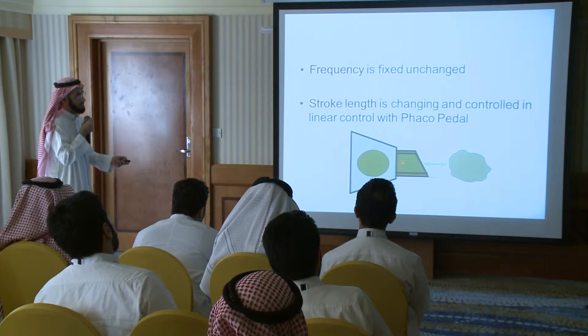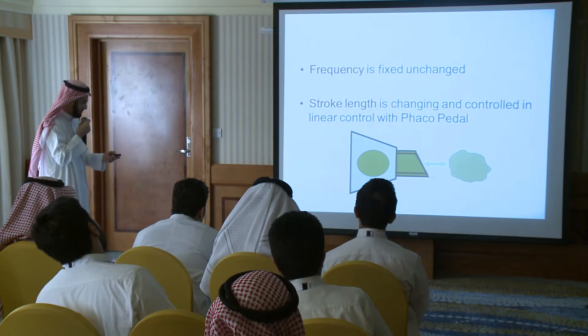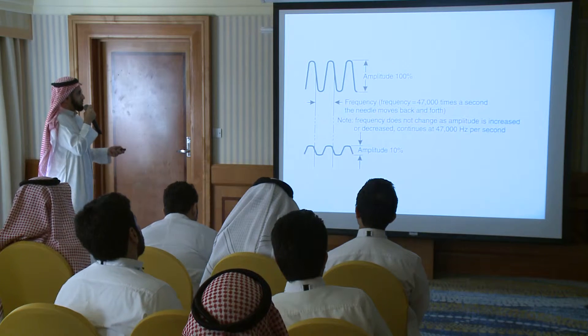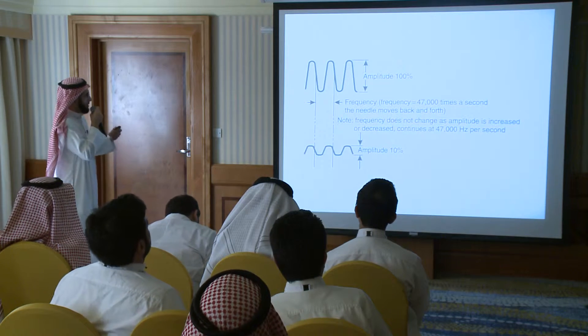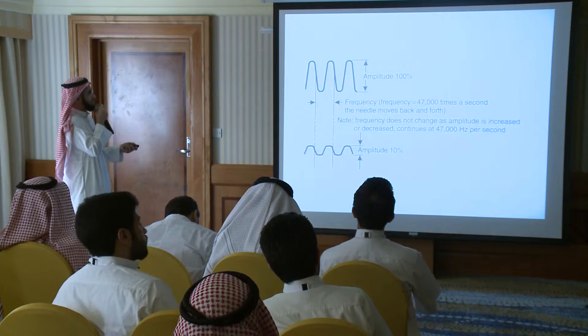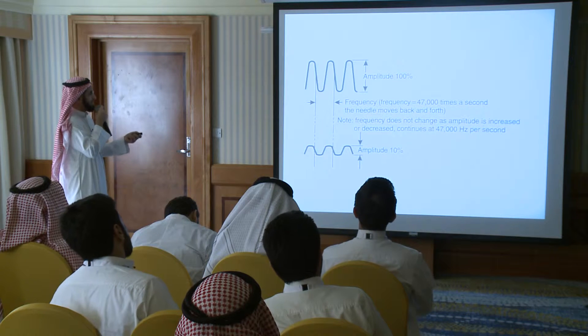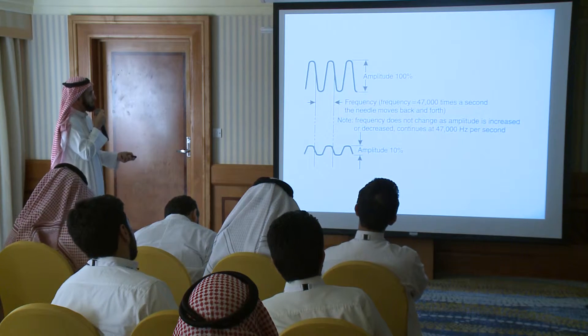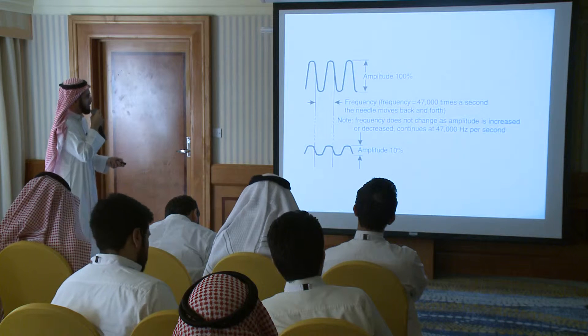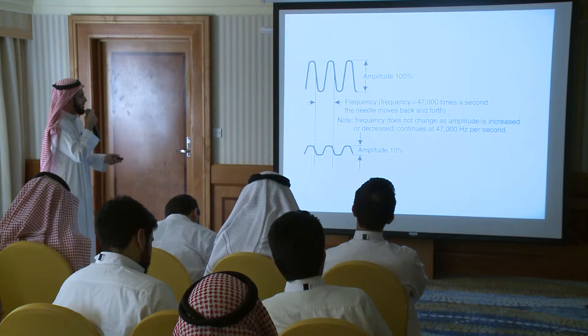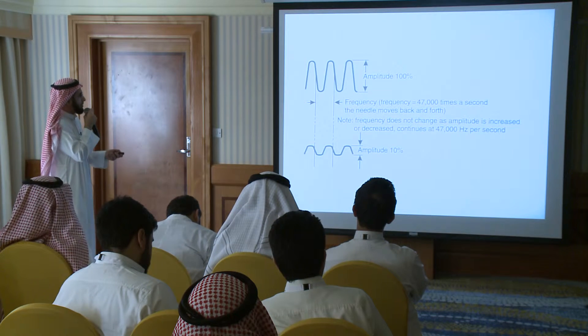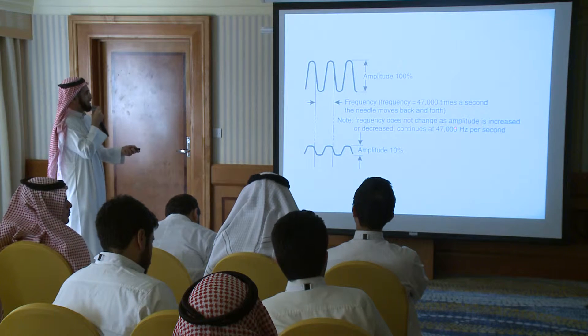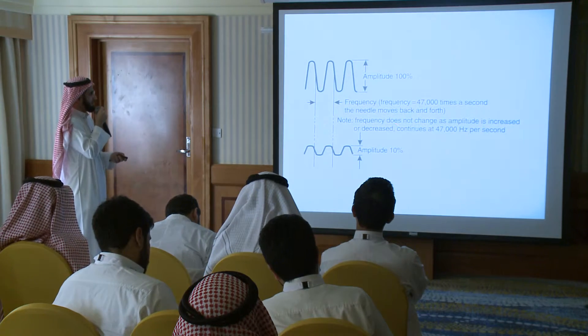We also have amplitude, which we can adjust up to 100% or even less. Most phaco machines operate at around 47,000 oscillations per second while oscillating the needle.